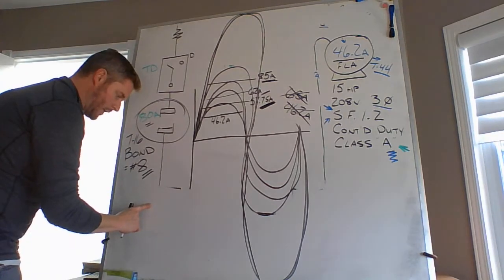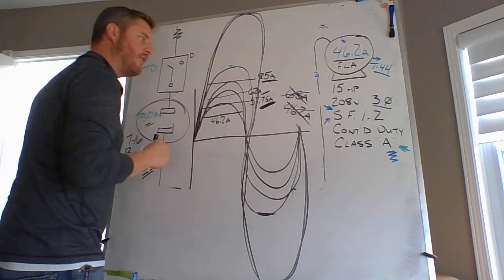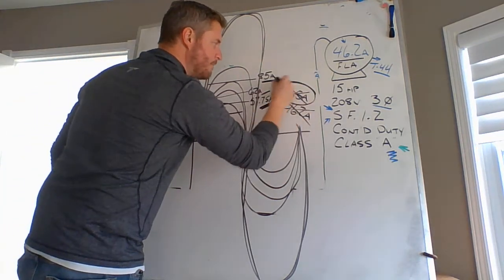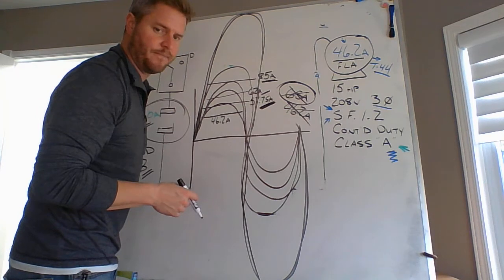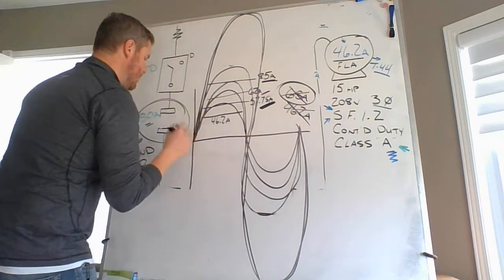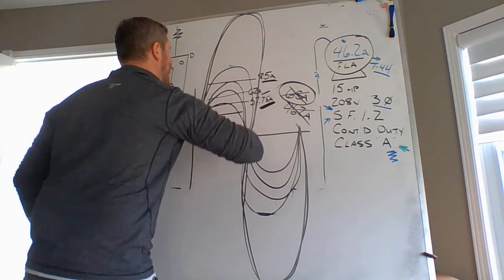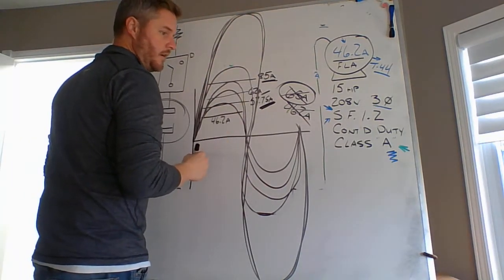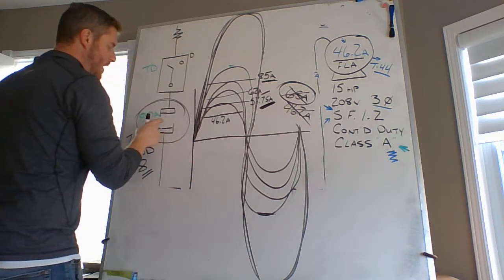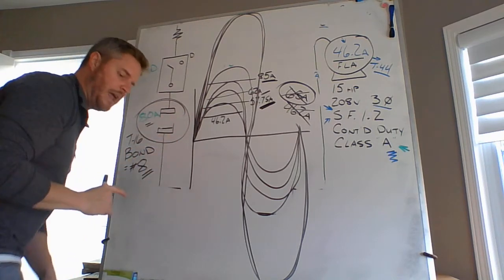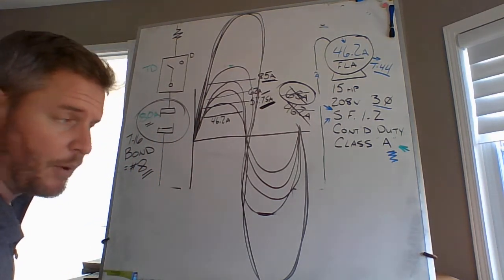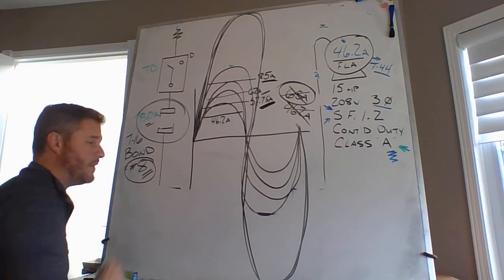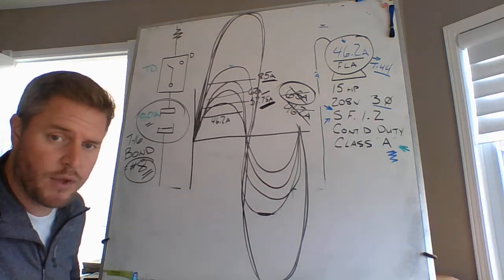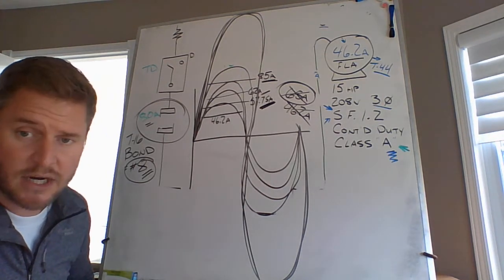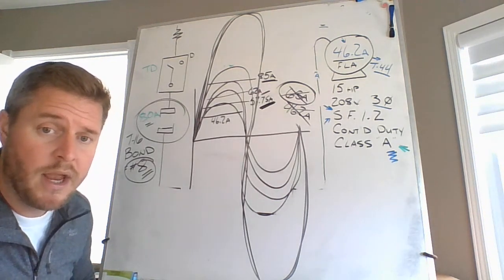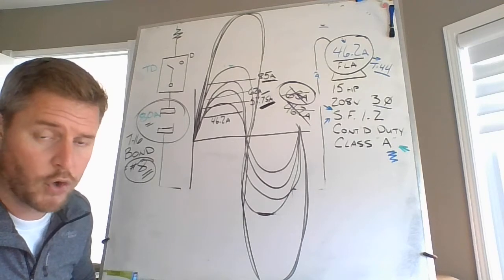Your overloads that were drawn over here protect your conductors because they were rated for 57.75, but your conductors are coming from table 2 at 65 amps. As soon as you have a short in your AC sine wave, it's going to exponentially increase. And that overcurrent device is going to open as fast as possible, because the reason why you install a number 8 bonding conductor right here is to facilitate the rapid operation of the overcurrent device, coming right back from basic section 0 definition. A bonding conductor is installed to facilitate the rapid operation of an overcurrent device.